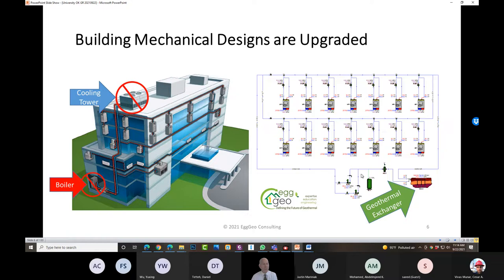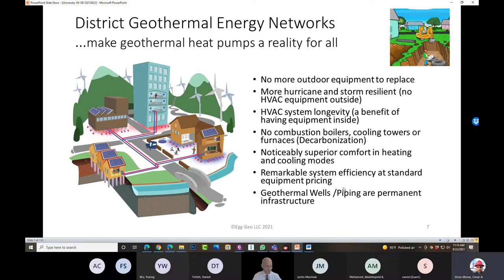These are eliminated and replaced with a geothermal exchanger, which I realize is kind of behind my head here, so I'll move to the side so you can see it. That geothermal exchanger or geothermal infrastructure is used to replace your combustion boiler, and it's used to replace your cooling tower. All that energy, instead of being exchanged with outside air, is exchanged with the ground.